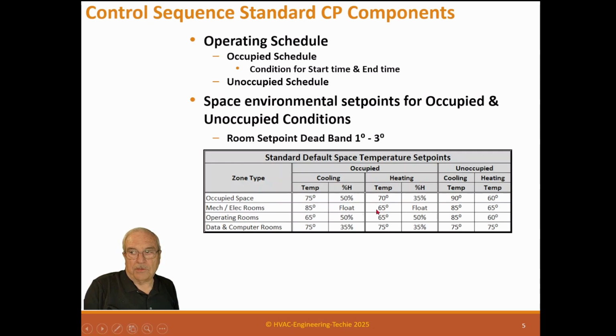Mechanical and electrical rooms are 85 degrees, 65, and floating for relative humidity. We don't care. Operating rooms are 65 degrees, 50% both for heating and cooling. Some operating rooms may have a control feature that allows them to keep it at 65 degrees and then run it up to 85 degrees as soon as they're done with the operation. Because 65 degrees is where the human body responds best to what they're doing. And as soon as it's all patched up, they want it warm for the patient to come up out of anesthesia and all that stuff. Data rooms are 75, 35 both.